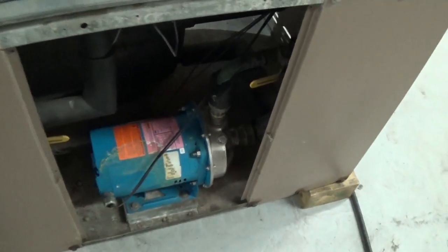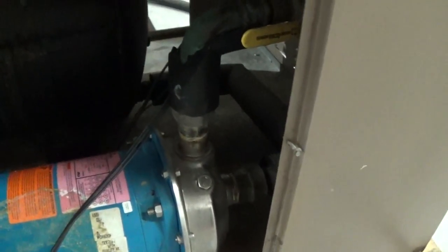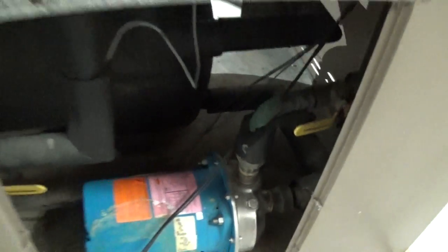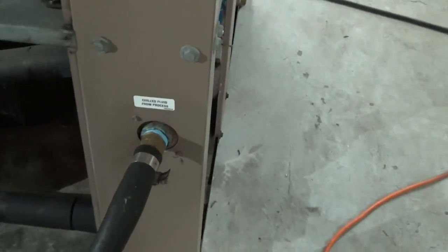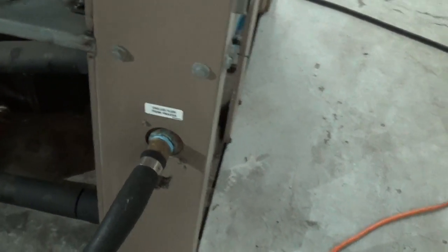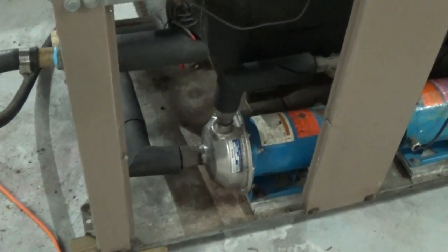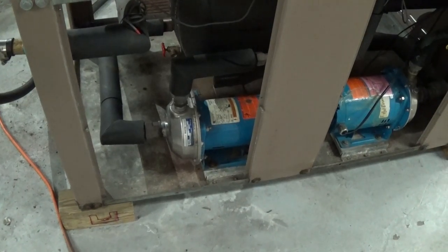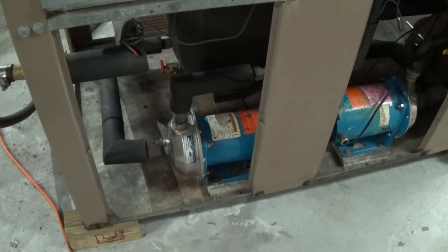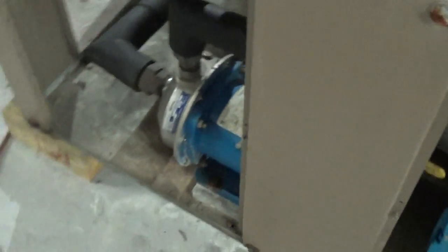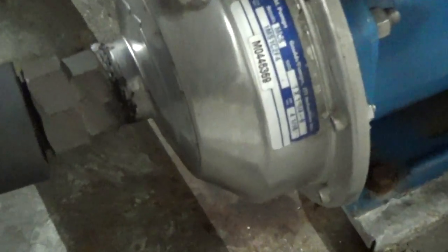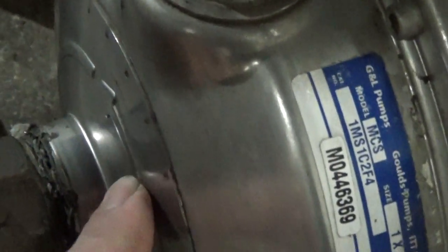And then we have the process pump, which also draws off the tank, and that discharges out to the process and comes back here where it says chilled fluid to process. The best way to confirm startup correct rotation is probably with this pump here, the recirculation pump. It's a two-man job. Have somebody bumping the contactor inside the control cabinet and look at the back of the motor here, or the shaft, and you want to match up with the rotation, which is embedded here on the volute, or the impeller housing as I call it.